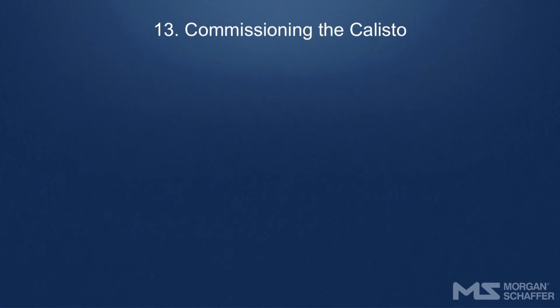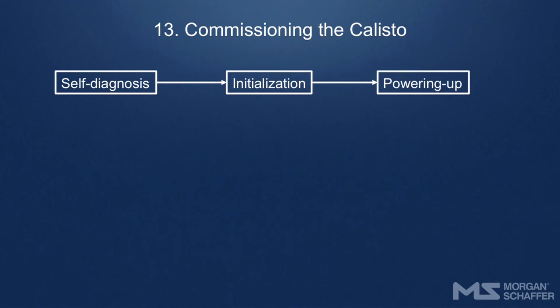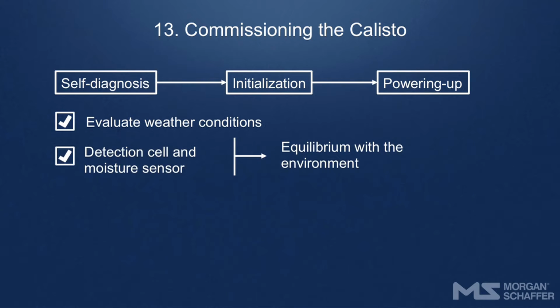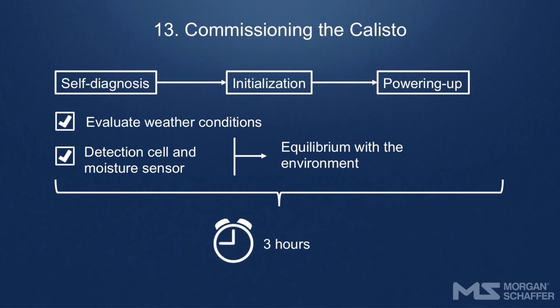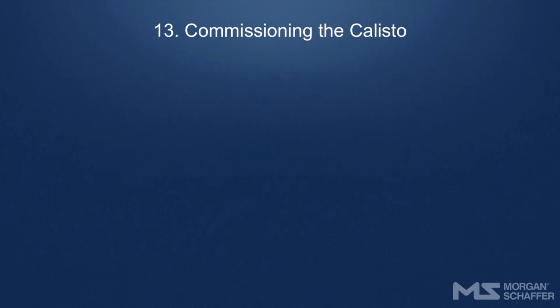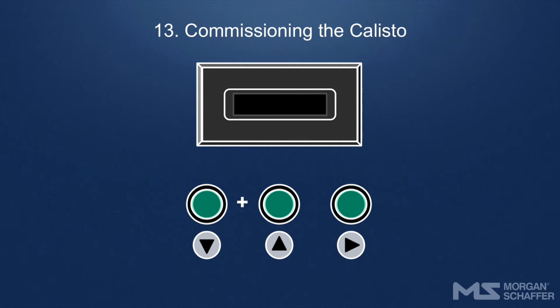When the Calisto 2 is started up or reset, the unit enters a self-diagnosis, initialization, and powering up sequence. This mode allows the onboard computer to evaluate weather conditions and allows the detection cell and moisture sensor to reach equilibrium with the environment. The initialization process takes 3 hours or 1 complete measurement cycle. Throughout the process, the display on the door will indicate H2 equals init.